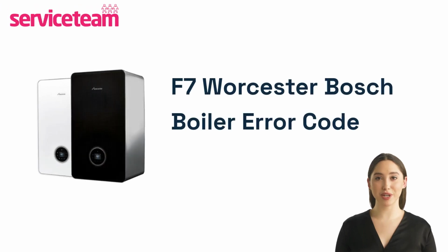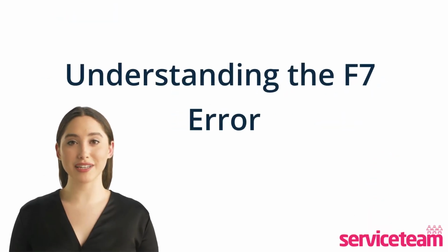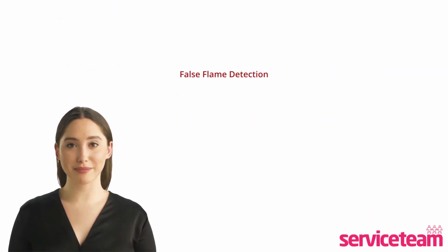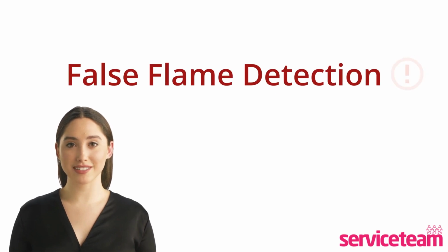Let's find out how to troubleshoot the F7 error code in the Worcester Bosch boiler. If your Worcester boiler is showing an F7 error code, it simply means your boiler shows a false flame detection within the system, when the boiler is switched off or inactive. This error can be puzzling, but understanding its possible causes is the first step to fixing this issue.